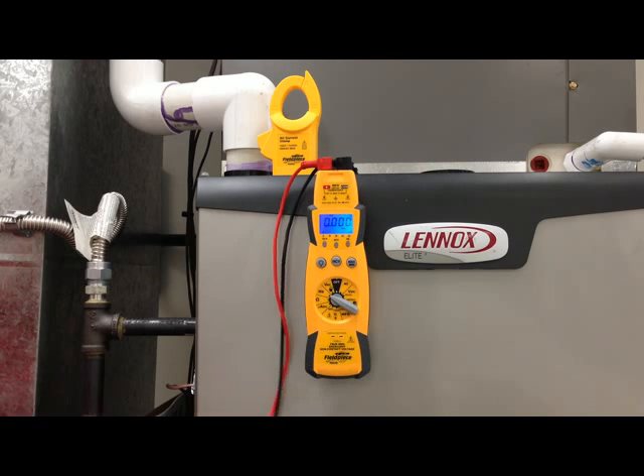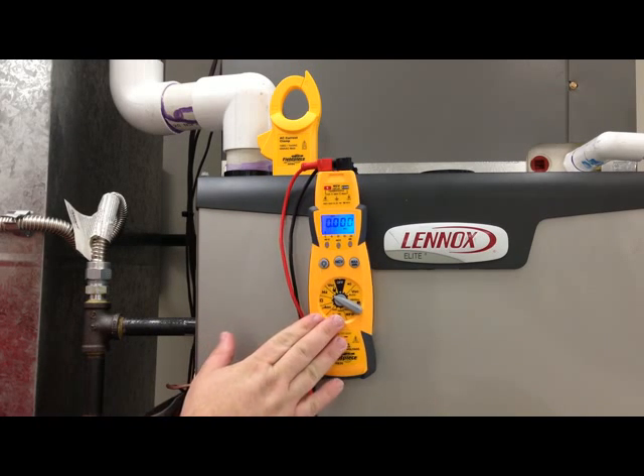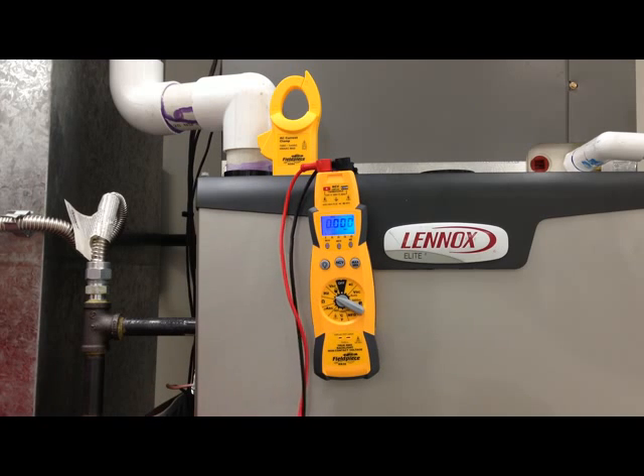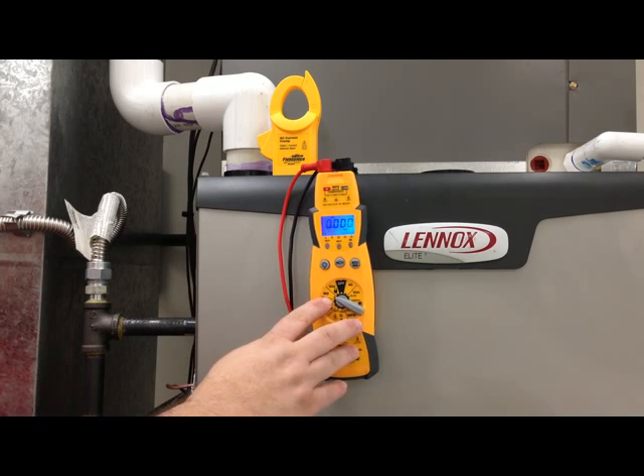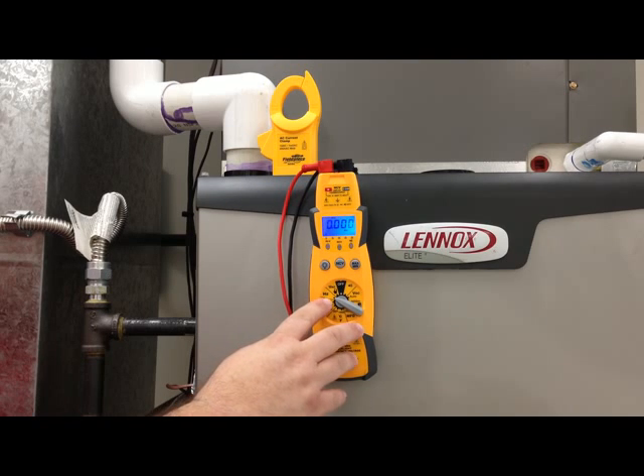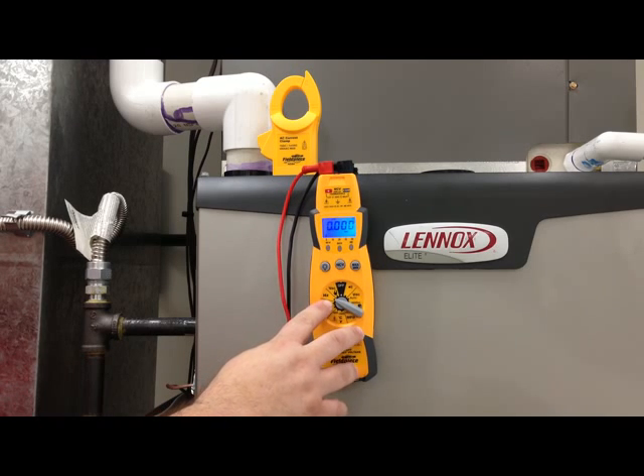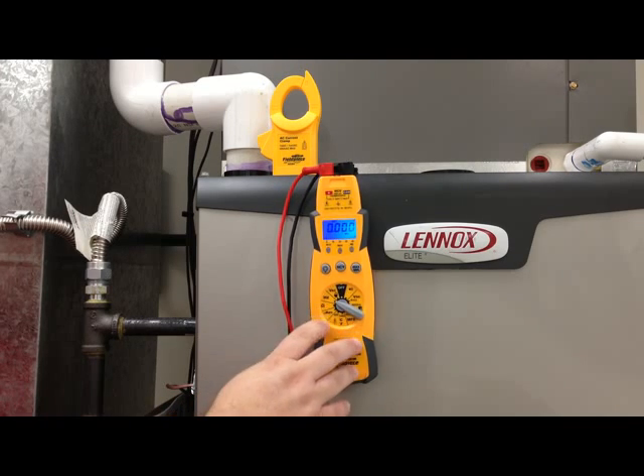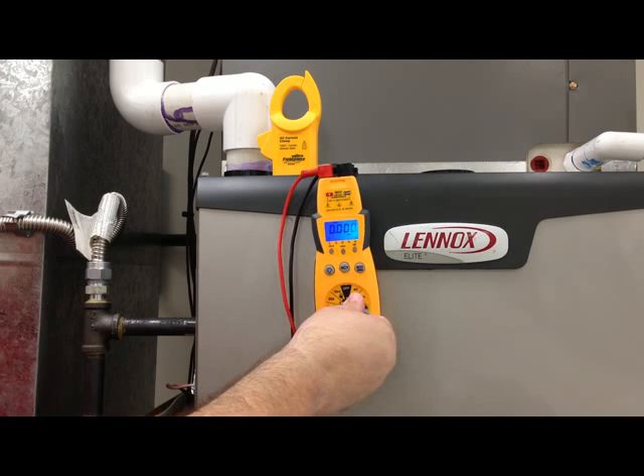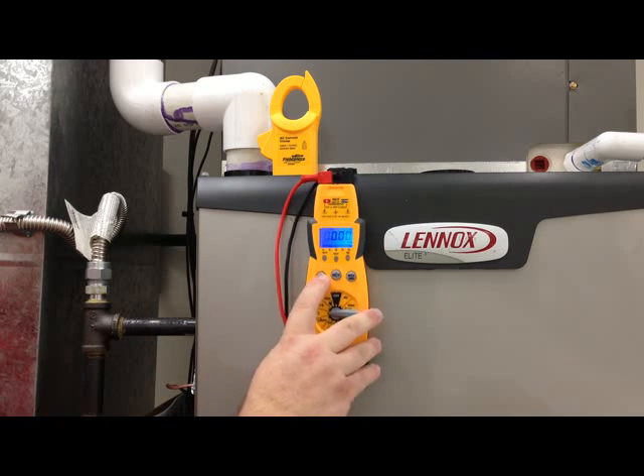And here we see the dial that says Hz. That stands for hertz, or the frequency of the electricity. How many times a second the alternating current is turning back and forth on itself. Now you may not use this on regular jobs, but if you're working on something like a VFD, a variable frequency drive, we alternate the frequency, or the number of times per second the alternating current turns back and forth, to vary the speed of a motor. Very important to know.